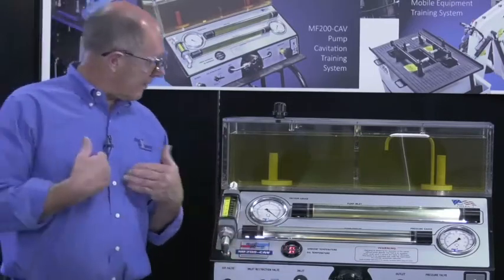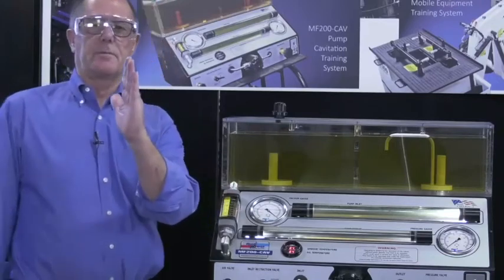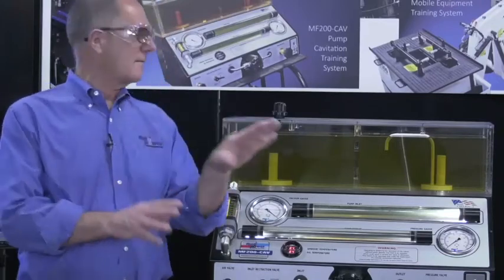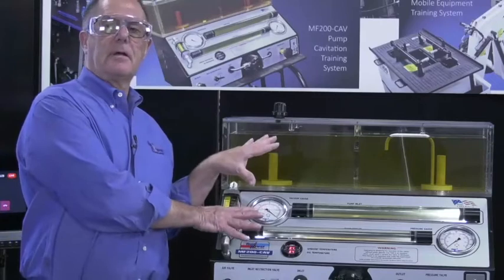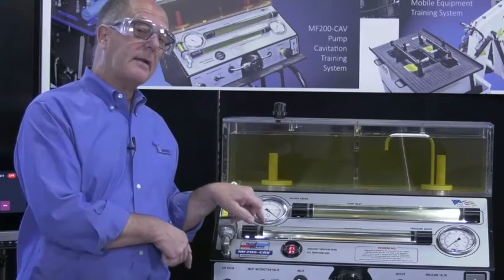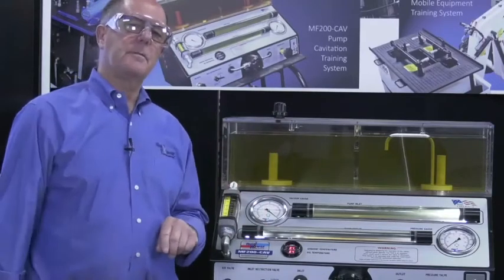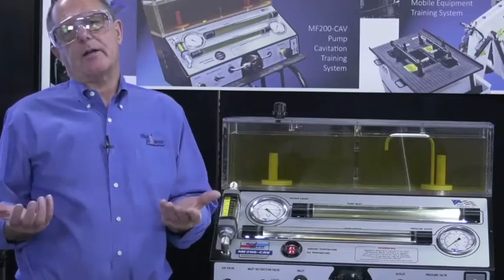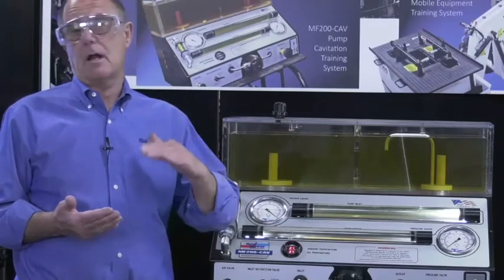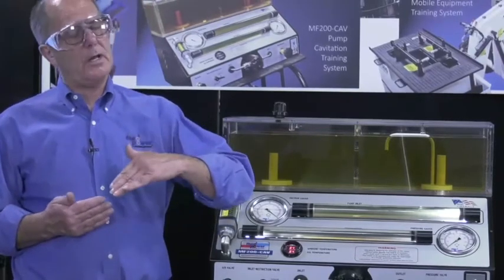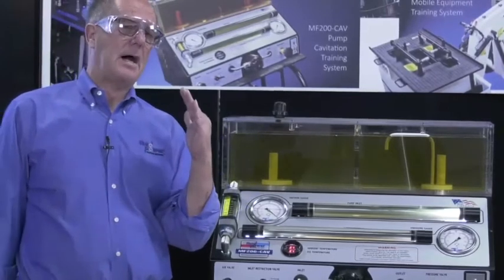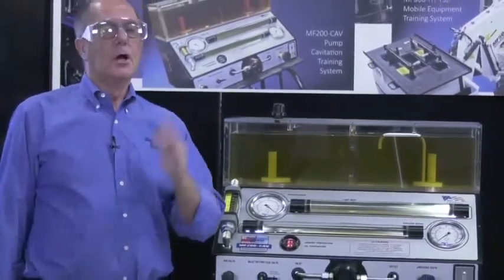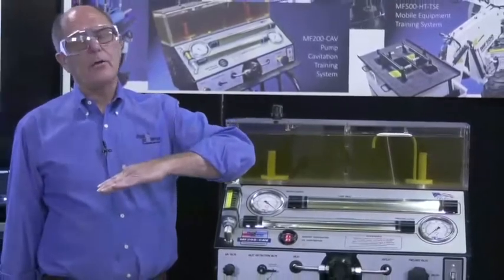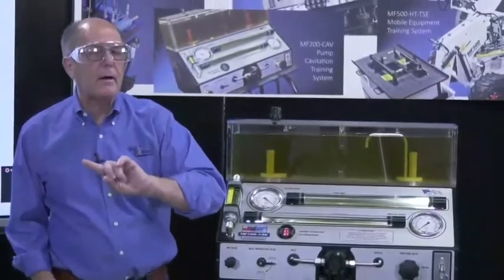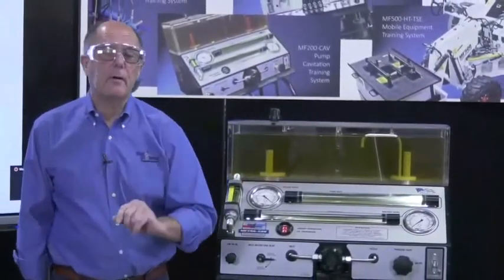Now I know we established our point of reference at 4 inches of mercury. So for the rest of this trainer's life, at this altitude, with that temperature, it'll run at 4 inches of mercury, which means if I came to this trainer next month and it was either lower, let's say it went to 3, or let's say it went to 5, I would know there's a problem. Because if it goes down, it's bad news. See, lower is not better when you have a point of reference, right?